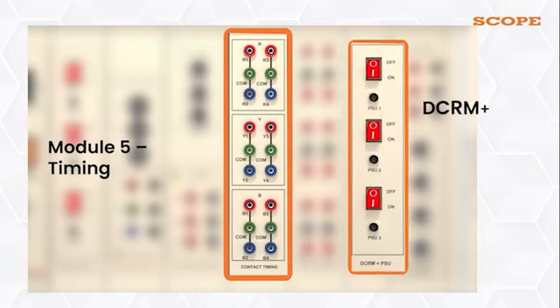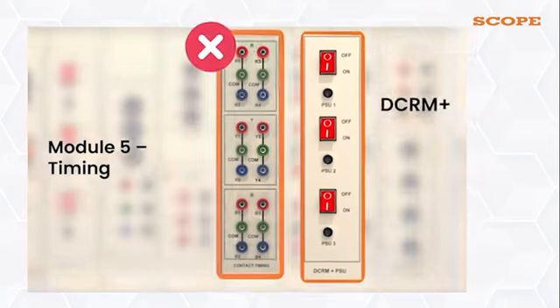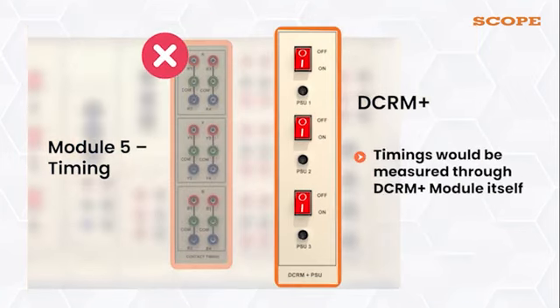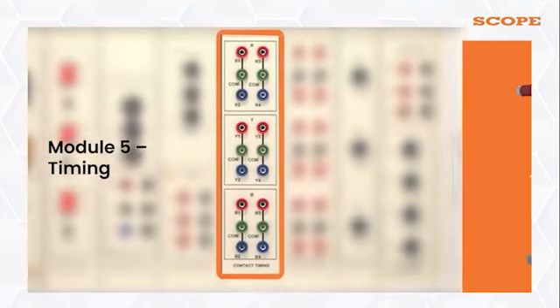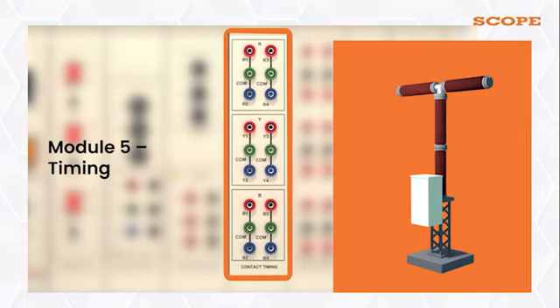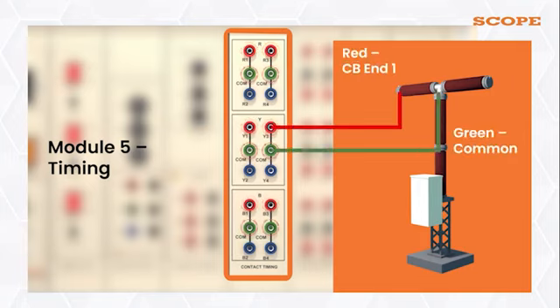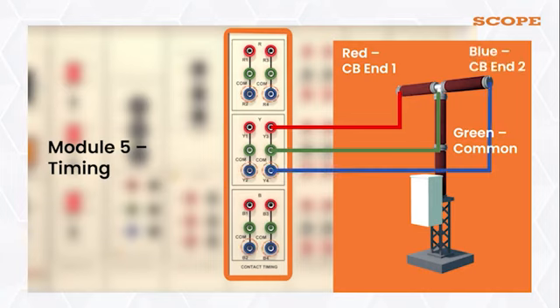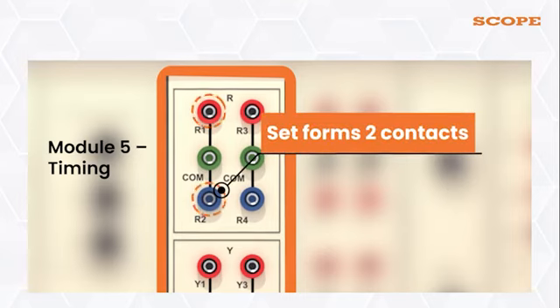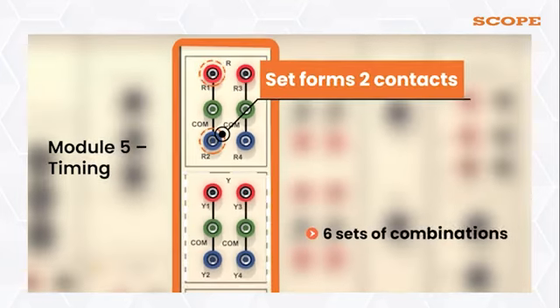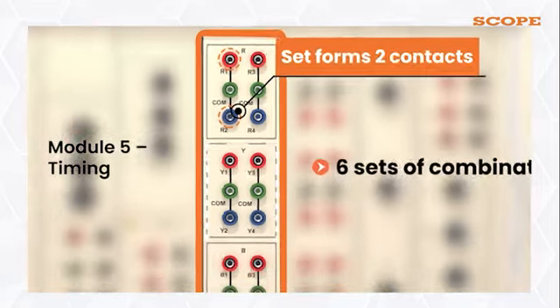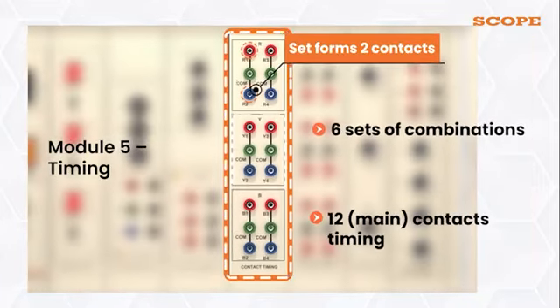When you would do the connection with DCRM Plus, the use of this module is not required. Timings would be measured through DCRM Plus module itself. The connector details of this module are as shown here. Red, CB end 1. Green, common. Blue, CB end 2. The above set forms 2 contacts, thus we can see there are 6 sets of combinations, thus the instrument can measure up to 12 main contacts timing.